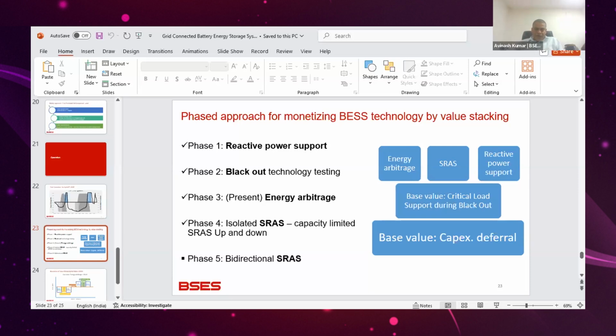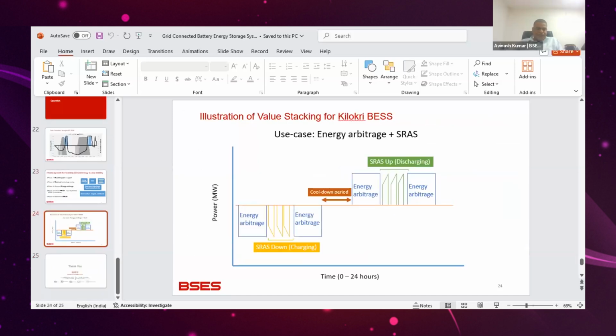Reactive power support from the battery is available. Energy arbitrage we have already discussed, and during a grid failure or blackout condition, we are able to meet the critical demand up to 20 megawatt from this system. The secondary result, ancillary services testing, is also completed. Closed loop and open loop: closed loop testing is completed with the NLDC, and we are evaluating the results. Then we can participate in the frequency regulation market also.